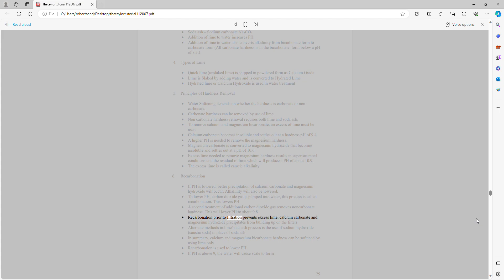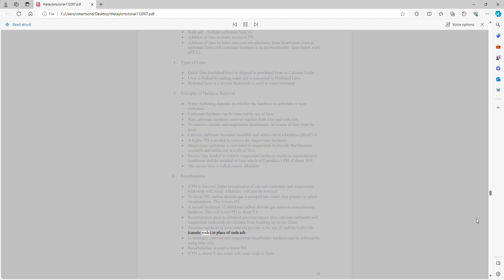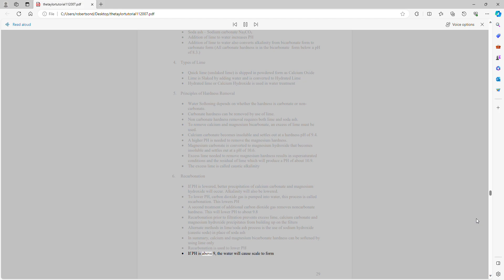Recarbonation prior to filtration prevents excess lime, calcium carbonate, and magnesium hydroxide precipitates from building up on the filters. An alternate method in the lime/soda ash process is the use of sodium hydroxide (caustic soda) in place of soda ash. In summary, calcium and magnesium bicarbonate hardness can be softened by using lime only. Recarbonation is used to lower pH. If pH is above 9, the water will cause scale to form.